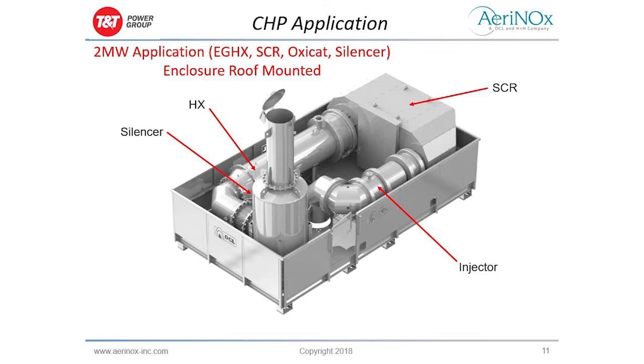An important piece here that most people tend to ignore or forget about is that each one of these components in the system has a way to reduce exhaust noise. The common methodology in the past is, well, I have exhaust noise, so I'm going to buy a silencer. That's fair, but remember, this catalyst bed has certain noise constraints it can apply. Sometimes the design of the heat exchanger can also control certain exhaust noise constituents, depending on the frequency we're trying to obtain. So it's important, when looking at the overall system, to take into account all the different factors involved.